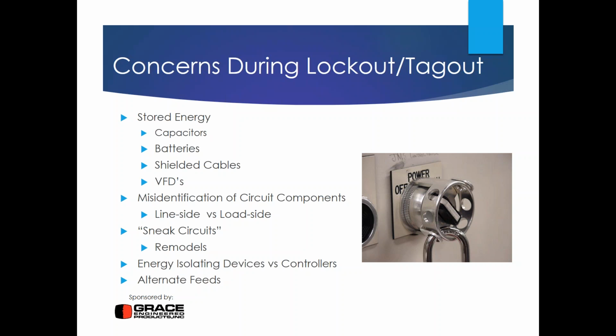But suffice it to say that most of the time you have a concentric neutral around the cable. Concentric meaning in a circle, and it is a neutral because if you actually added up those strands, they are sized as a neutral for the phase conductor. When there is a shield around the outside of it, it acts in every respect like a capacitor, and it can store a charge that can be fatal. Variable frequency drives also often have capacitors or other storage devices in them that can backfeed or release energy, and those also need to be isolated if you're going to be working on those pieces of equipment.